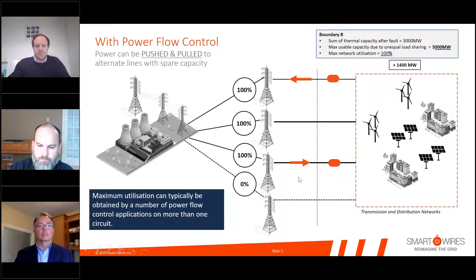Traditional solutions for this, you'll all be familiar with, are phase shifting transformers. They've been installed not just in Canada, but across the world for over 50 years at this stage. And really what they do is they can be installed in a circuit and change the phase angle between the sending end and the receiving end on a particular line. They do this in the classic power flow equation shown. They impact the sine delta aspect of that equation, and by doing that you change the power flow.